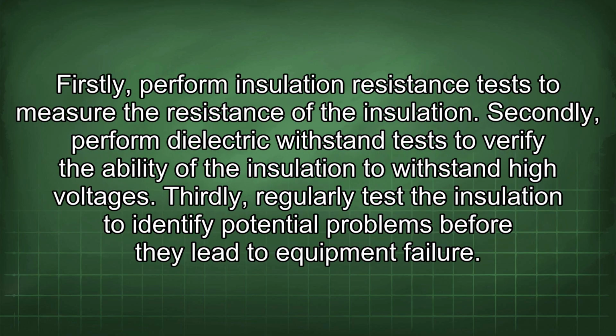Insulation testing is used to assess the condition of the insulation within switchgear. Firstly, perform insulation resistance tests to measure the resistance of the insulation. Secondly, perform dielectric withstand tests to verify the ability of the insulation to withstand high voltages. Thirdly, regularly test the insulation to identify potential problems before they lead to equipment failure.